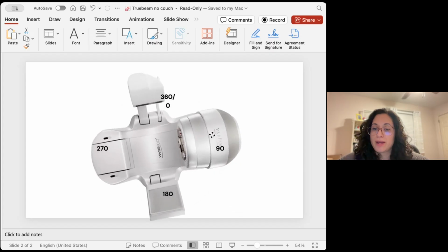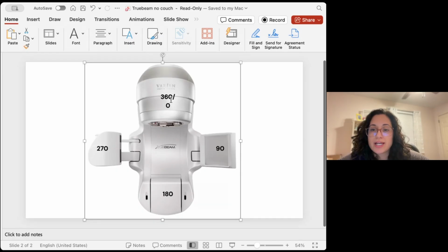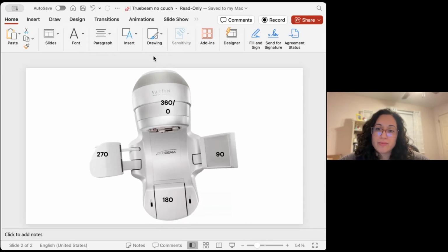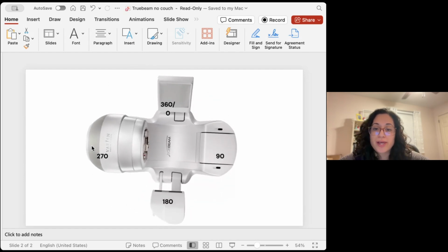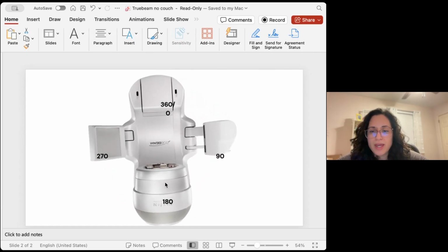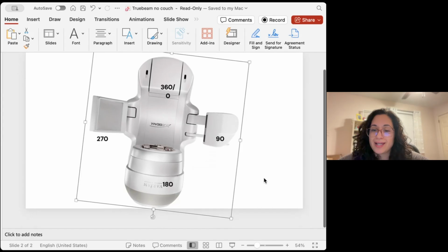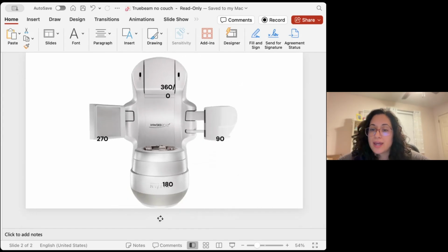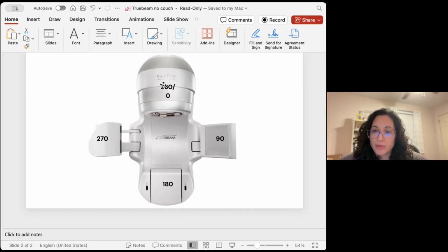And like I said, it can go back counterclockwise. So now instead of 0, it's going to be easier to reference this location as 360. And now the numbers will start to go down from 360 to like 350, 340, so on and so forth. And a true lateral would be 270 and then back down to 180. And this, at least for Varian TrueBeams I can speak to, would be known as 180E, so extended. And again, it can't go further past. It gets stopped here and it has to go back around the other way.